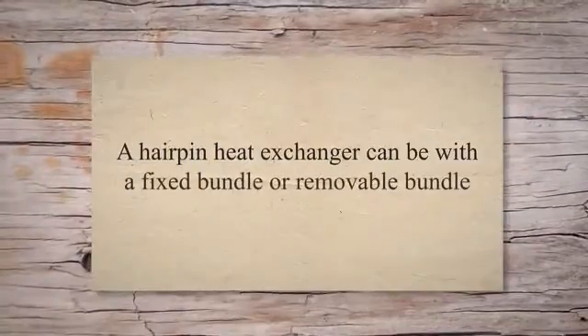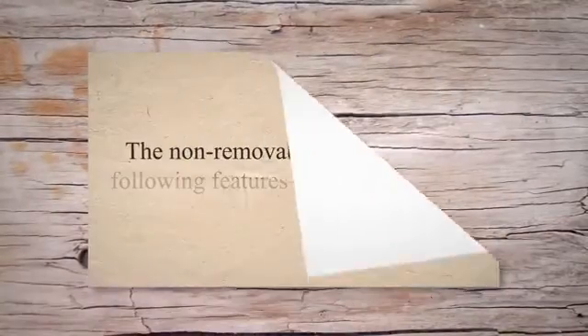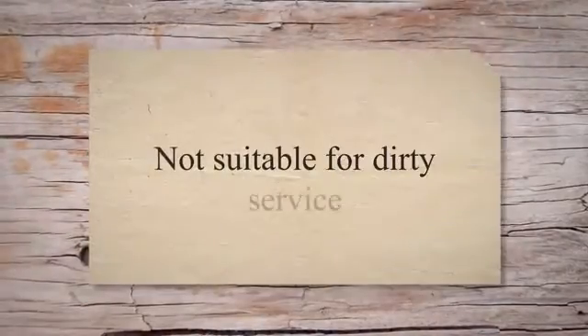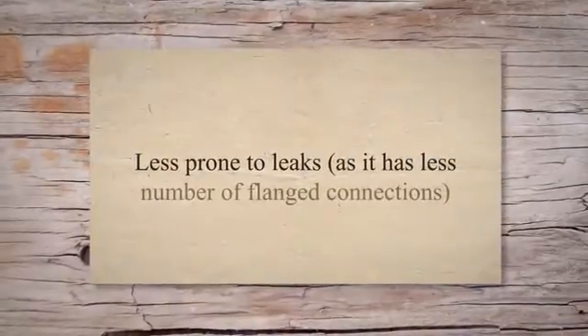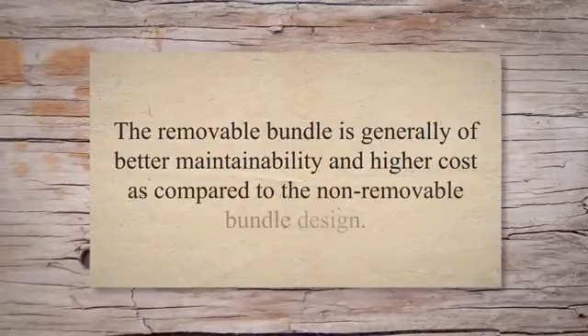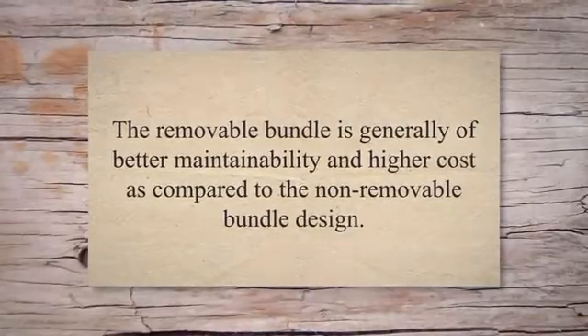A hairpin heat exchanger can have a fixed bundle or removable bundle design. The non-removable bundle features lower cost and a fixed tube sheet, but is not suitable for dirty service, has poor maintainability, and is less prone to leaks due to fewer flanged connections. A removable bundle can be either with common closure or separate closure, and generally offers better maintainability at a higher cost compared to the non-removable bundle design.